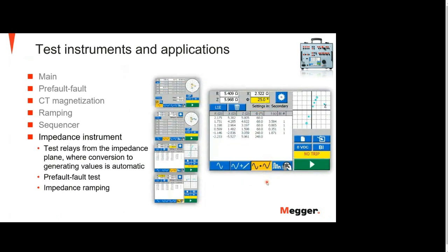And then we have the last instrument, the impedance instrument. That's where you can test distance protection, for example. So you're working in the impedance plane, and you're setting your values in impedance, resistance, reactance, or phase angle. And the Sverker 900 will calculate what kind of current and voltage it should generate according to your settings. So you set these values, whatever you would like, in the impedance plane, and Sverker will calculate by itself what voltage and what current it will inject into, for example, the distance protection. So it's quite easy.